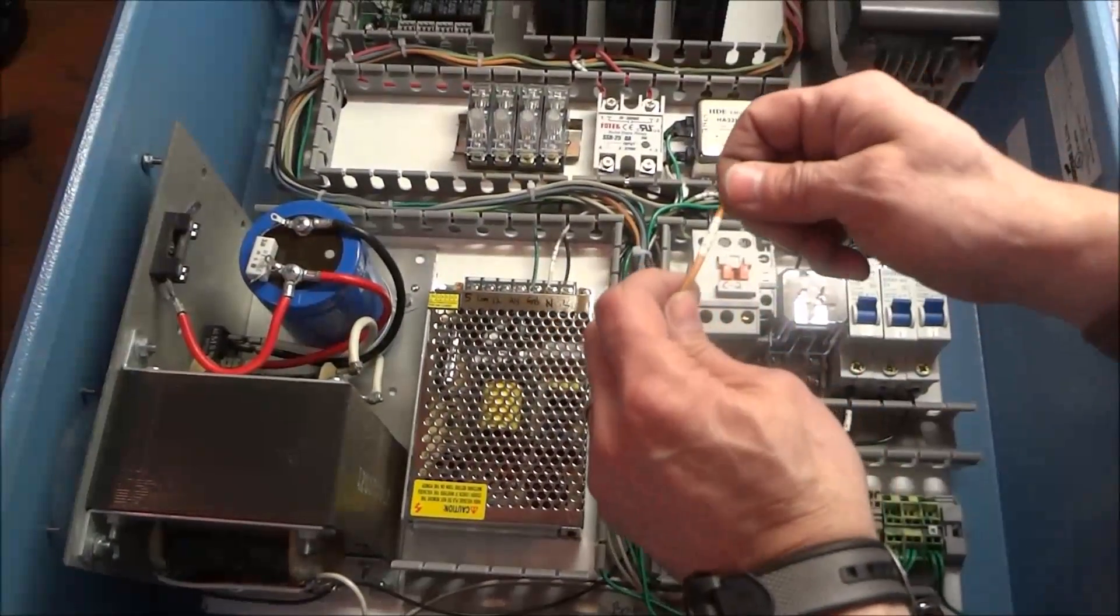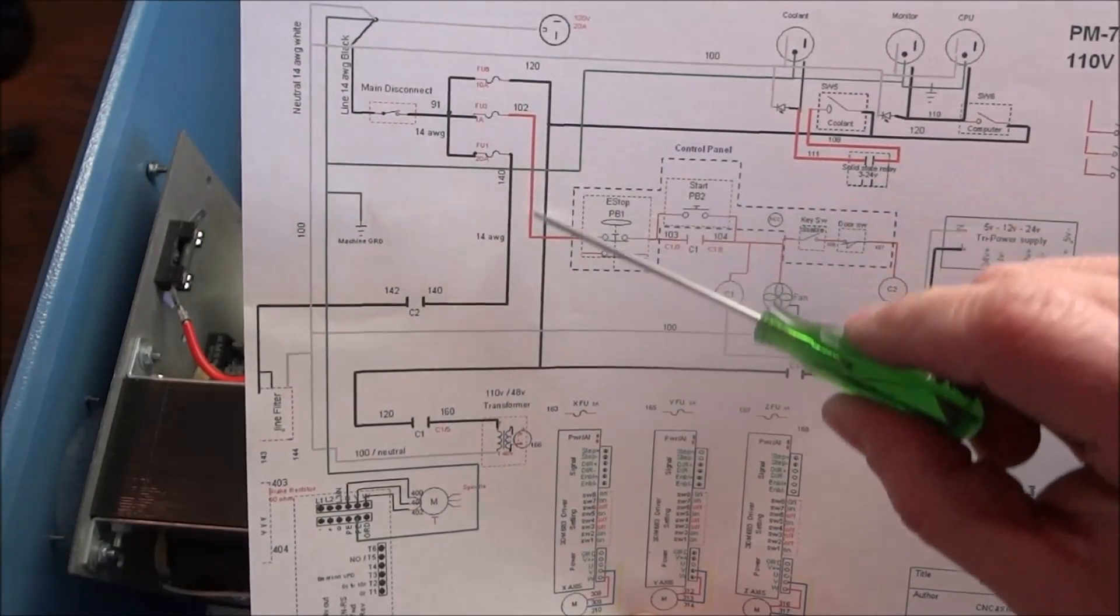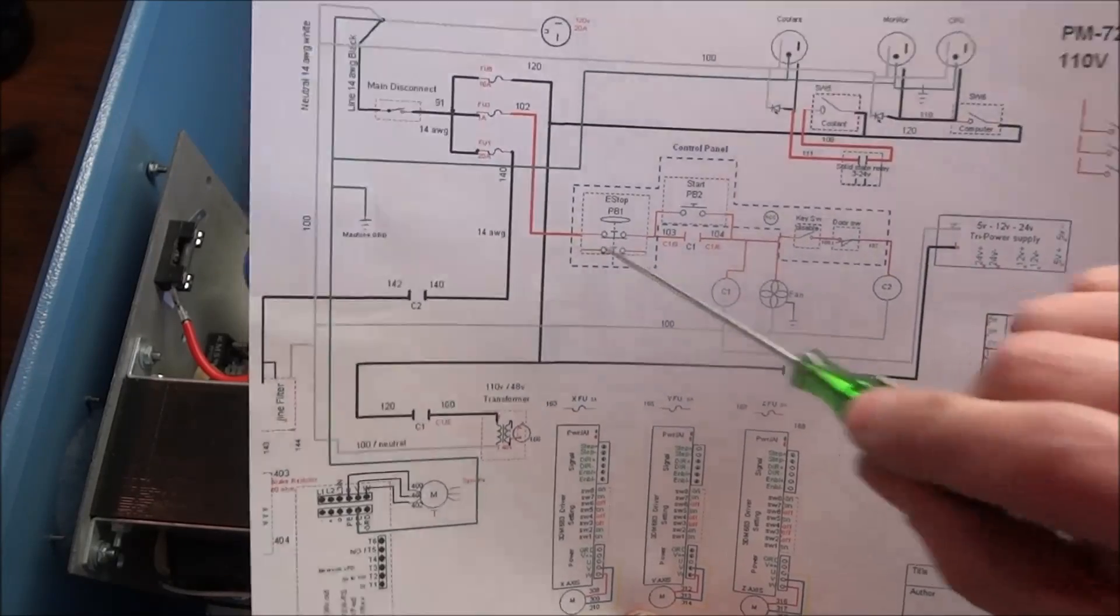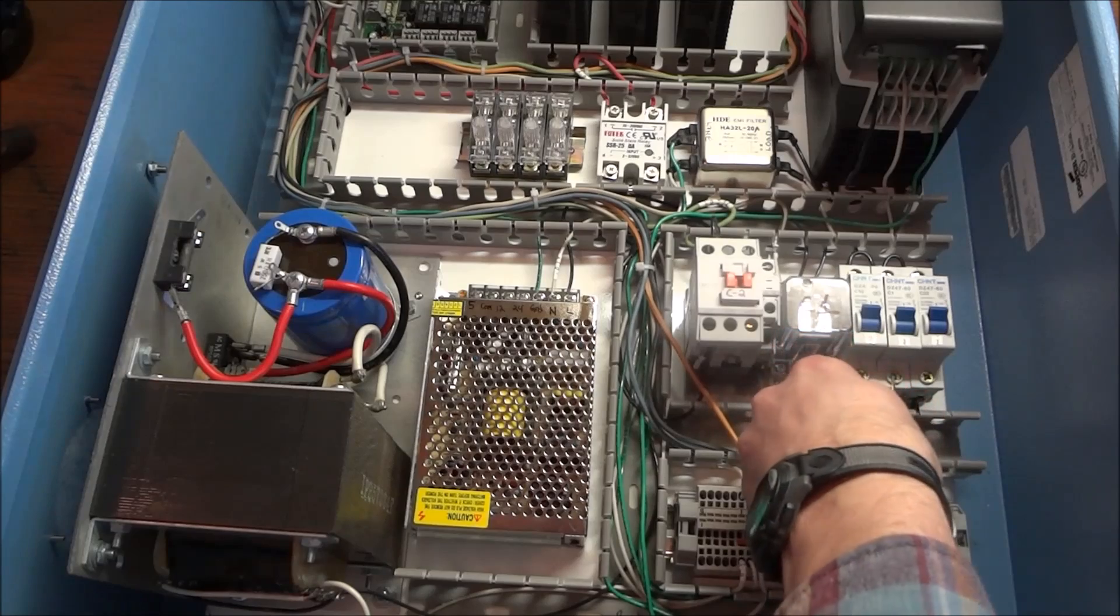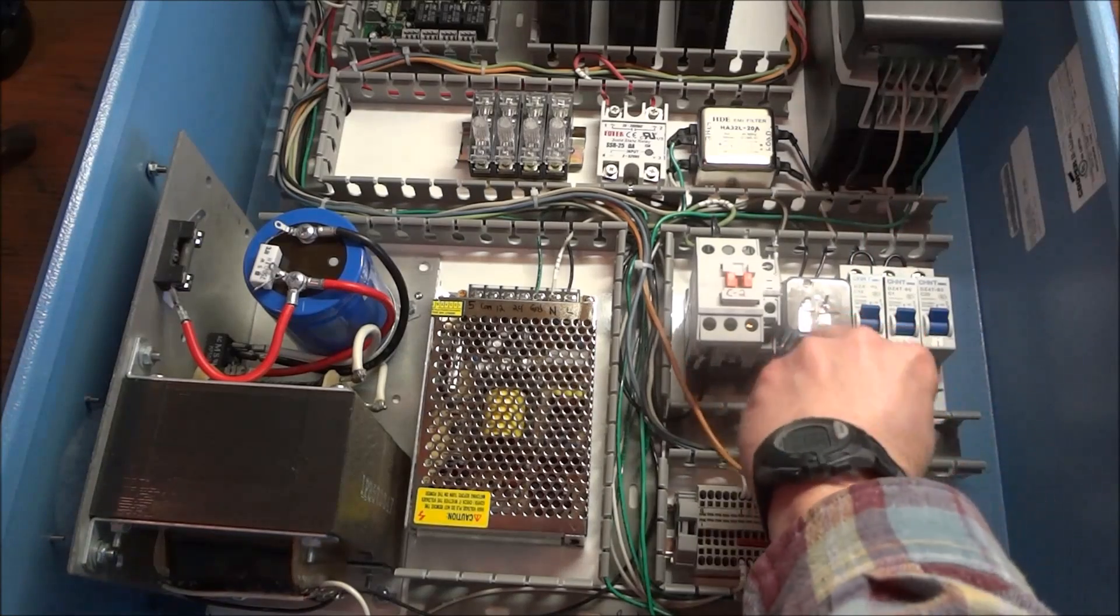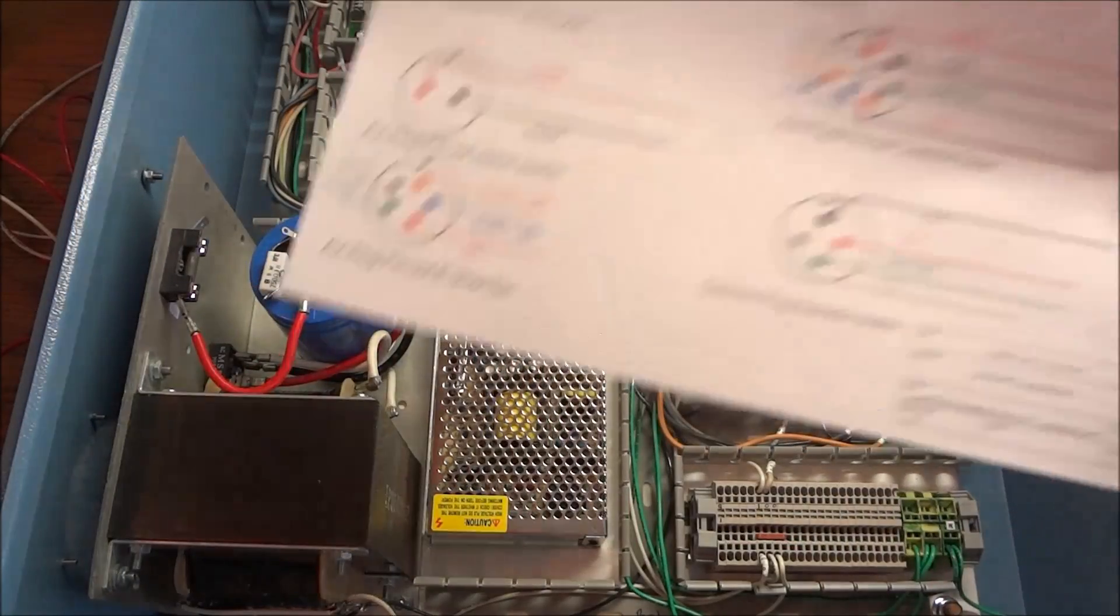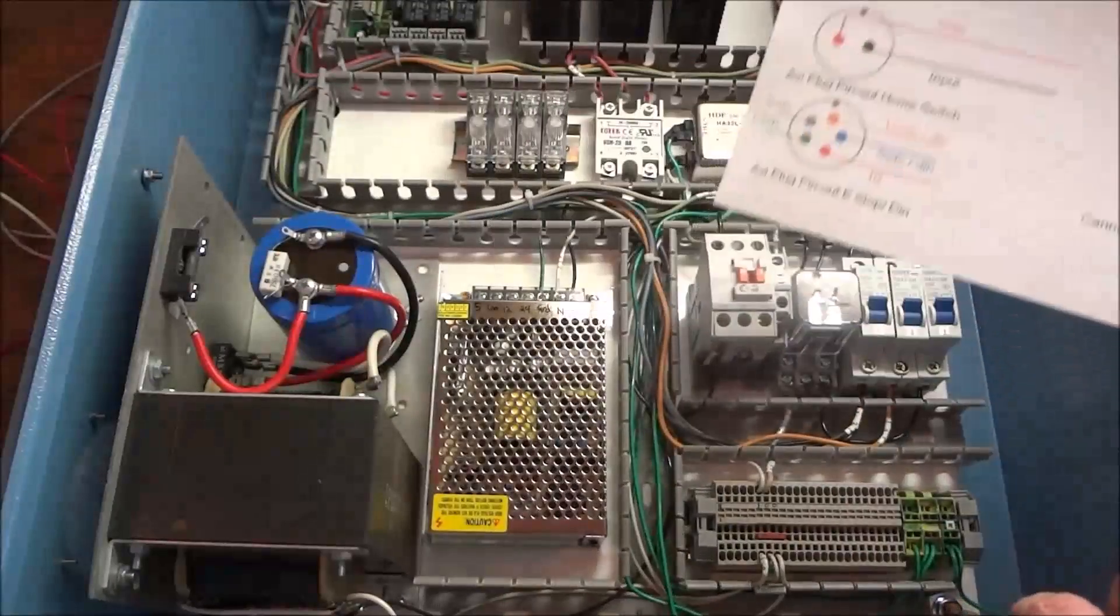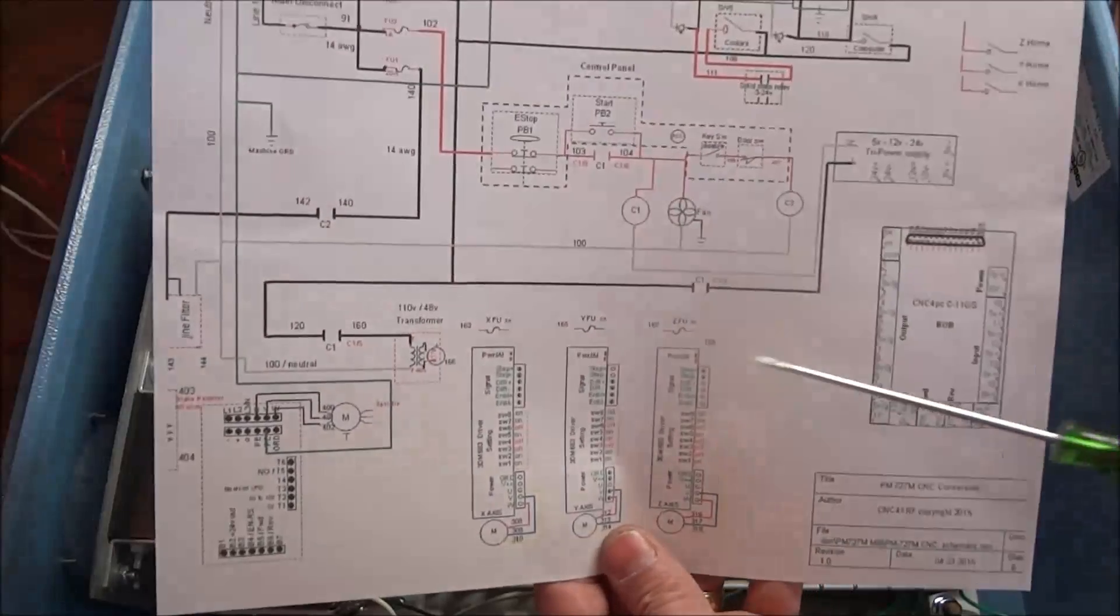Next we have wire 102. 102 goes to fuse 3. This is our 1 amp fuse. Actually it's a circuit breaker now. 1 amp. And this goes straight up to our control panel to our e-stop. And this provides power to our control circuit. So this goes to fuse 3. Okay. Take care of that. Okay now that we have all 8 of these wires connected inside our enclosure for our control circuit. There's also some secondary wiring that we need to go ahead and tidy up at this time.